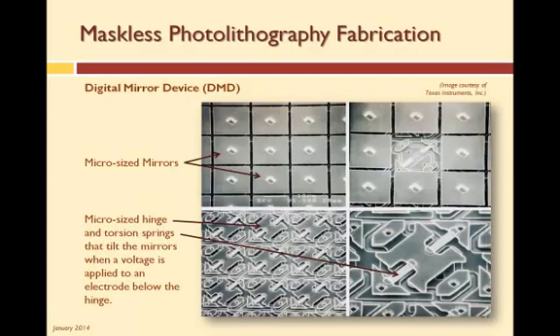The third process we are going to briefly discuss is the more recent maskless photolithography process developed by NimbleGen Systems. In this process, digital mirror devices, or DMDs, are used in place of the mask. Here is a micro-sized digital mirror array from a larger array of about a thousand mirrors. These same devices are used in InFocus projectors as well as the large digital projection systems used in movie theaters. Each of the micro-sized mirrors are placed on top of a micro-sized hinge suspended with a torsion spring. Underneath the hinge is an electrode or electromagnet. When the electrode is energized, one side of the hinge is pulled toward the electrode, causing the hinge and thus the mirror to tilt. When the voltage is removed, the torsion spring returns the mirror to home position.